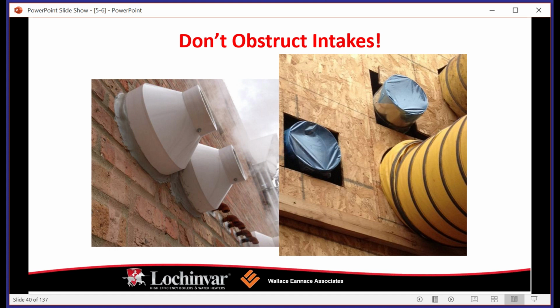Very important to remember too is snow line. So if you're venting and you're in a subsurface application and you punch out through a sidewall and you come out 3 inches above grade and you live in a part of the country where there is significant snow accumulation, you're going to have issues, because when the flue or the fresh air intake get restricted, you're going to have all sorts of combustion issues. You have a lot of failures. And again, you would be surprised how often this happens.